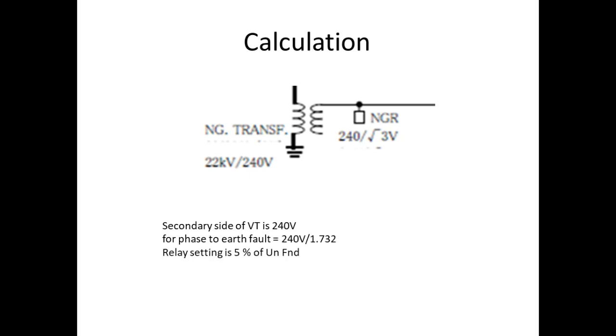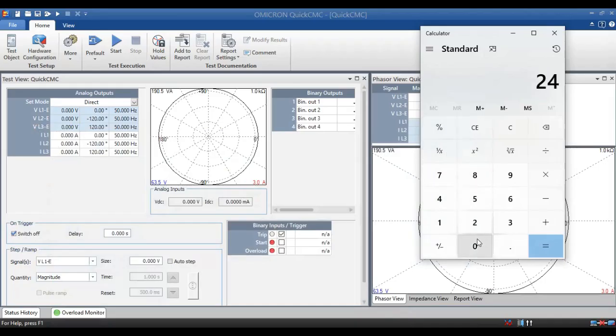For relay testing, we have to inject and check the secondary voltage alone. The secondary voltage is 240 volts. This voltage is achieved if it has only phase to earth fault. Now I am going to simulate phase to earth fault, so I have to divide by 1.732 and multiply by the set percentage.